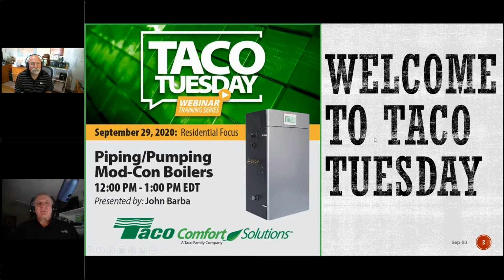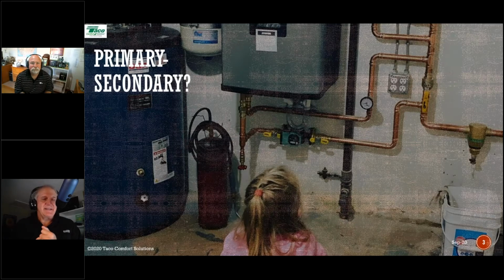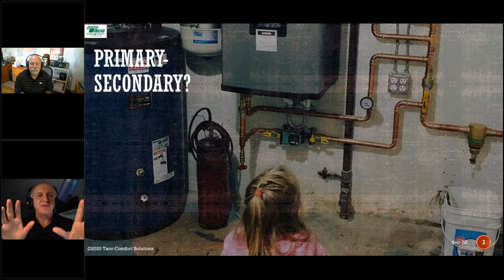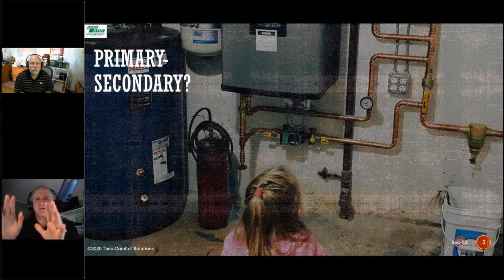So when we talk about piping up modulating condensing boilers, you could look at literally any ModCon boiler manufacturer's instruction manual, which I know we all look at, right? We all look at the instruction manual before we break into putting that thing together. But you can look into virtually anyone's manual, and they may be drawn differently, but if you take a good look at them, the piping schematics are pretty much similar. It's primary, secondary piping like we see here, but with a little bit of a twist, okay? With a little bit of a twist.